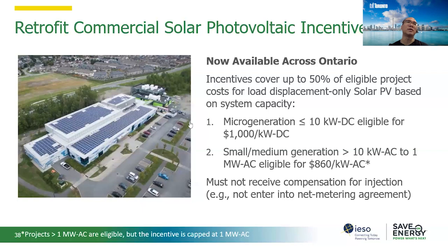In terms of electrical upgrades - right now we're in Ontario, working with net metering or load displacement, so these are all behind-the-meter systems. Generally, we do not need to upgrade the whole electrical system. In projects similar to the one I showed with the single line diagram, we do need to upgrade the splitter to fulfill the 125% rule laid out by the electrical code. That's the only upgrade needed on some sites. On other sites, we just need to add the proper size of disconnect to connect to the building.